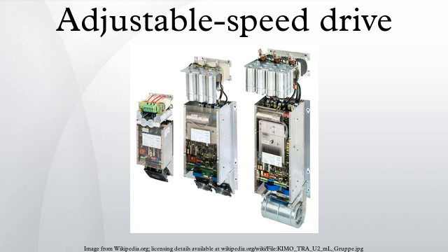Eddy current drives. An eddy current drive consists of a fixed-speed motor and an eddy current clutch. The clutch contains a fixed-speed rotor and an adjustable speed rotor separated by a small air gap. A direct current in a field coil produces a magnetic field that determines the torque transmitted from the input rotor to the output rotor. The controller provides closed-loop speed regulation by varying clutch current, only allowing the clutch to transmit enough torque to operate at the desired speed. Speed feedback is typically provided via an integral AC tachometer.